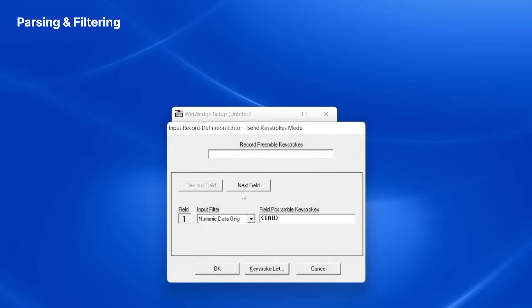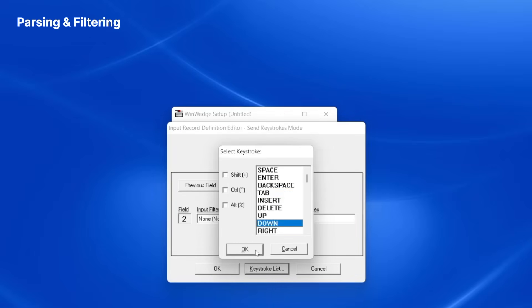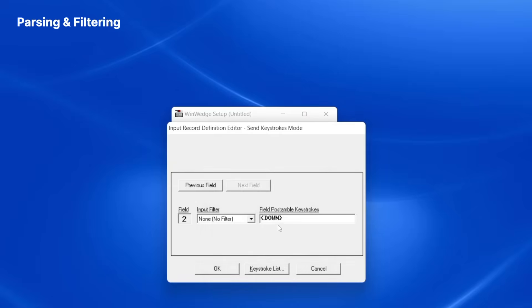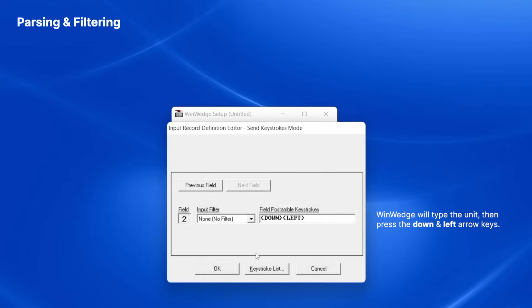I then click Next Field to set the parameters for the second data field which contains the units. For this field, I'll leave the filter option set to None. After the units are entered in Excel, I want to return the cursor to the original column in the next row down. To accomplish this, I add a down arrow keystroke and then a left arrow keystroke in the Field Postamble Keystrokes for Field 2. This simulates the keystrokes that I would type if I were manually entering the data in Excel.